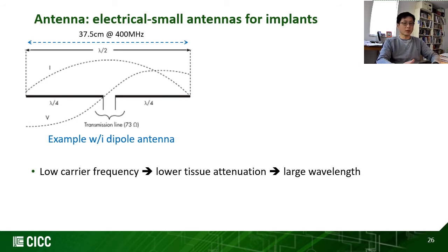The loss inside the body increases significantly when the frequency is above 1 GHz, as we already introduced in the previous section. That is why sub-gigahertz frequency is preferred for the implantable radio. One very popular frequency choice is 400 MHz. We can calculate that at 400 MHz the half wavelength is roughly 37 centimeters in air. When it is put inside the tissue, the half wavelength reduces to roughly 5 centimeters because the permittivity is higher.